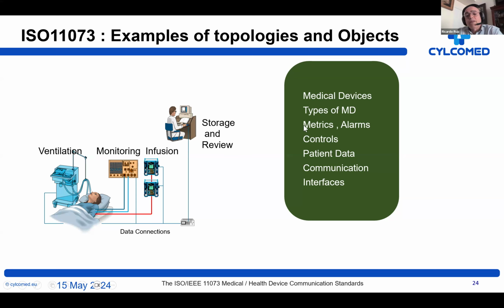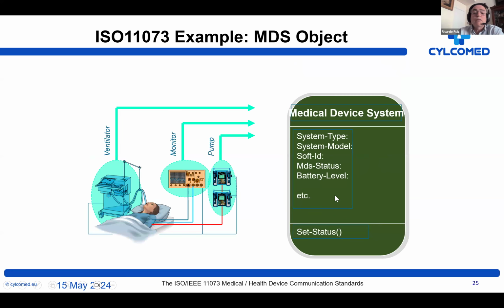So we have different types of information, from metrics, like the temperature value, to alarms. If, for example, the systolic pressure is higher than a certain value. We may control remotely a particular device. The standard allows for this, to make remote control. And of course, we can incorporate patient data into the system, and the stack of the ISO 11073 has solutions for standards on communication and solving the interfaces between different types of protocols at different levels.